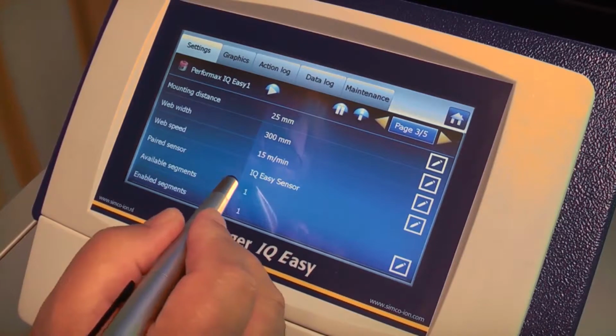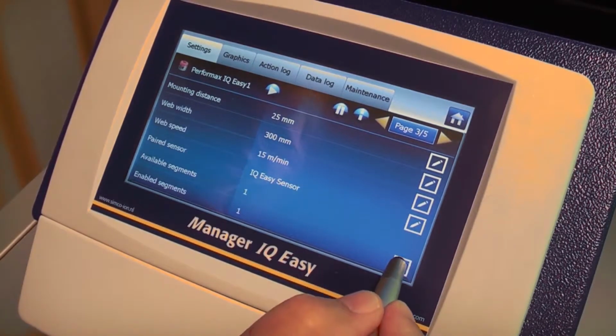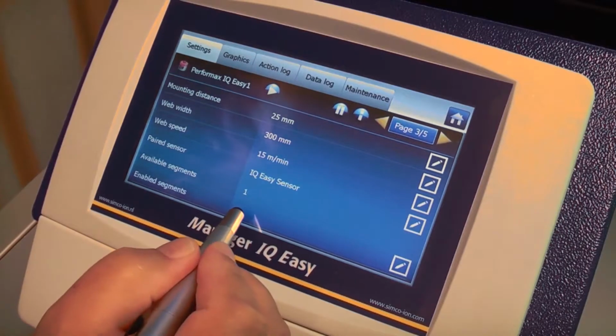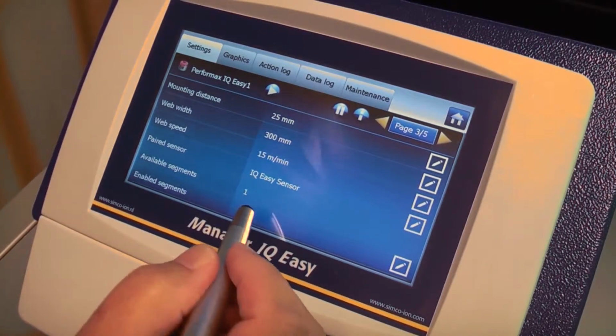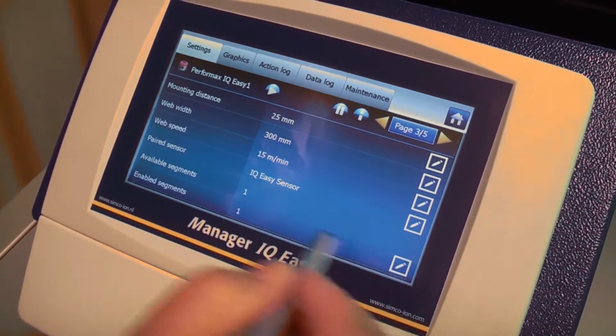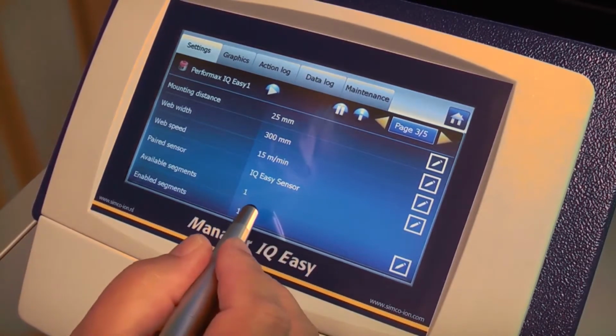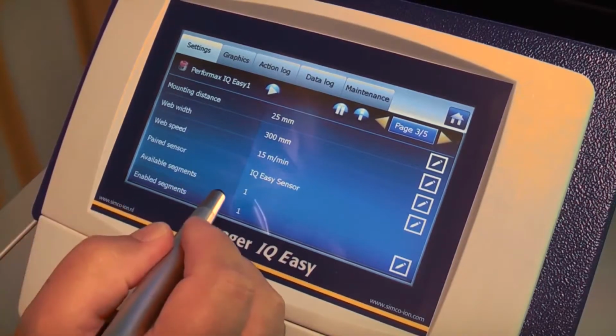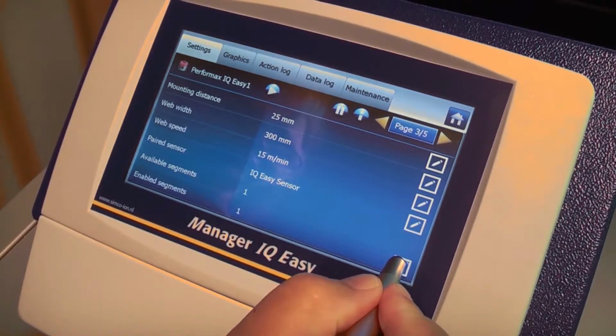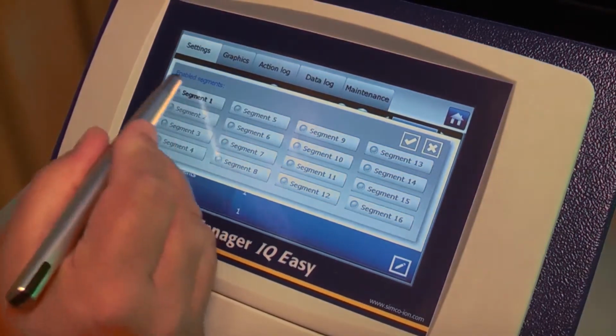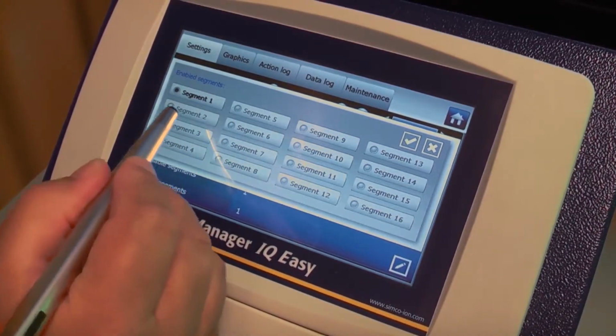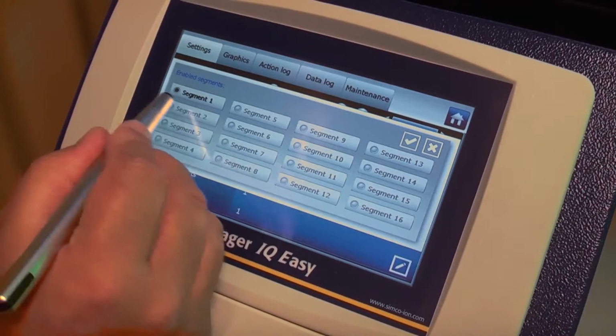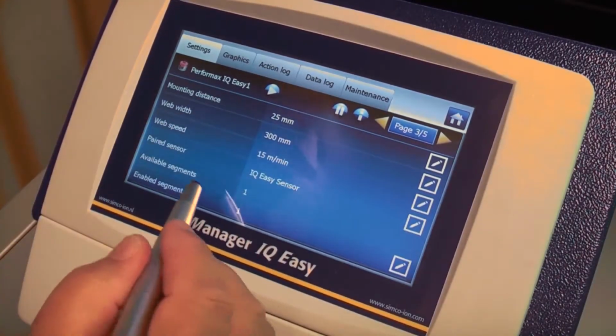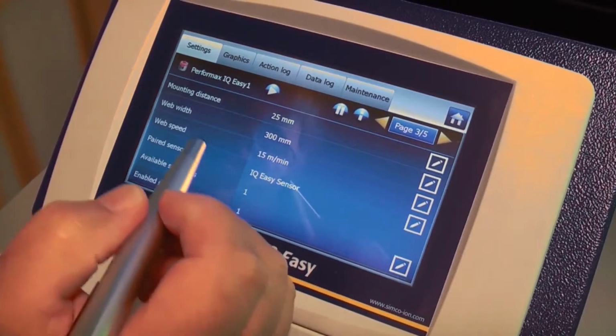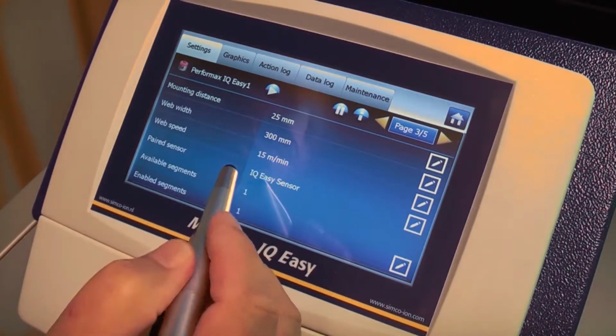If you have a sensor with more than one segment, you will have to choose which segments you want to be active during a production run, because it can happen that if you have 4 sensors and you are running a smaller material, only 2 sensors are measuring data on the web. In this case you'll have to go into this menu and select the segments that are actually measuring the web and make them active. So once we have set up these parameters, in principle the static bar is ready to run.